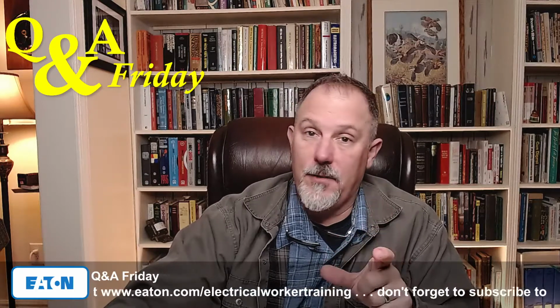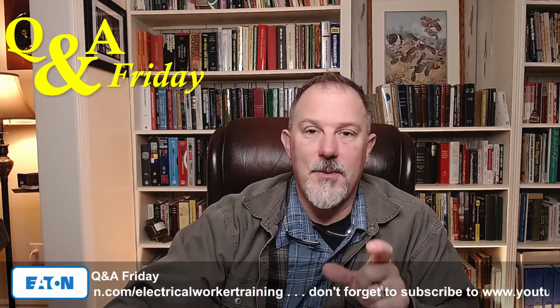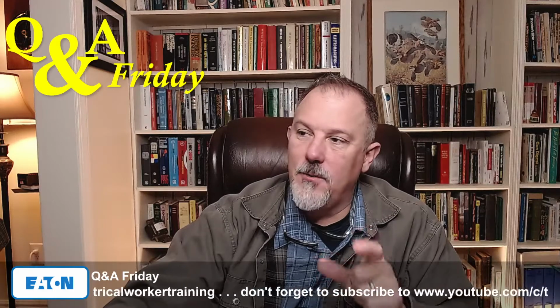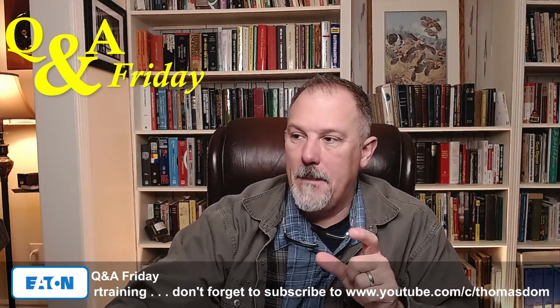And also the other thing is, like when you're doing conduit fill calculations... John McCamish, I got a good one for you: circular mils in table 8. Table 8 has circular mils. How are you calculating circular mils with the diameter values?